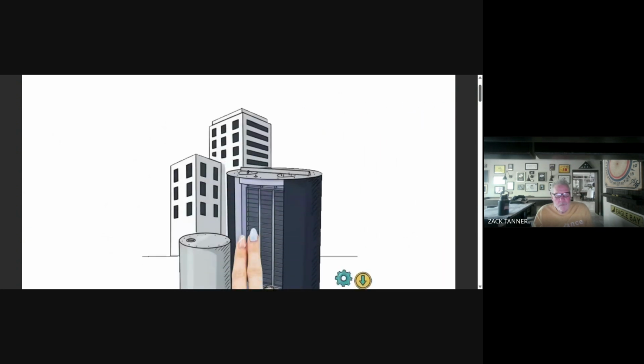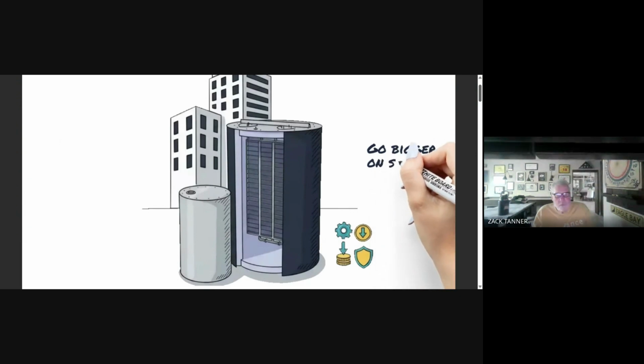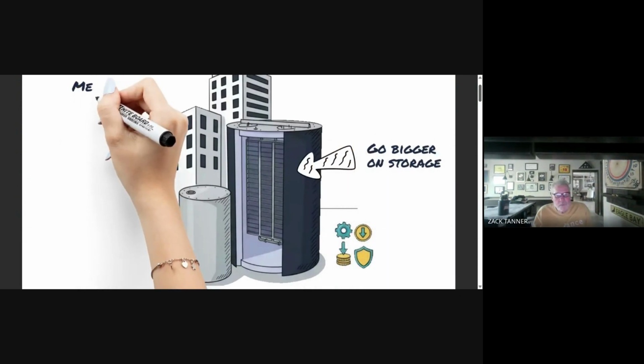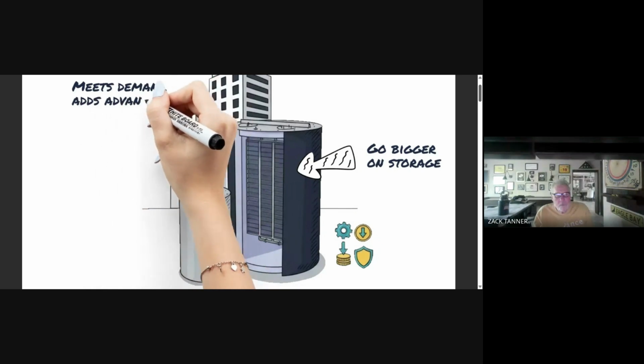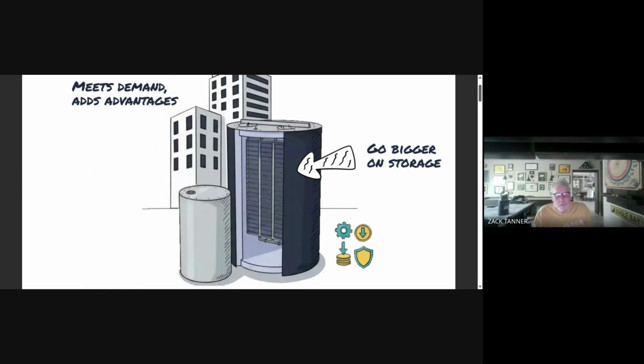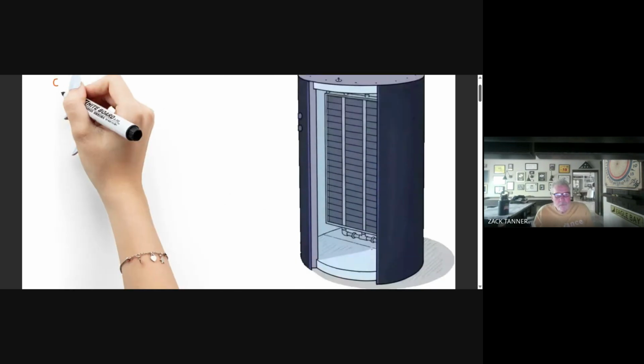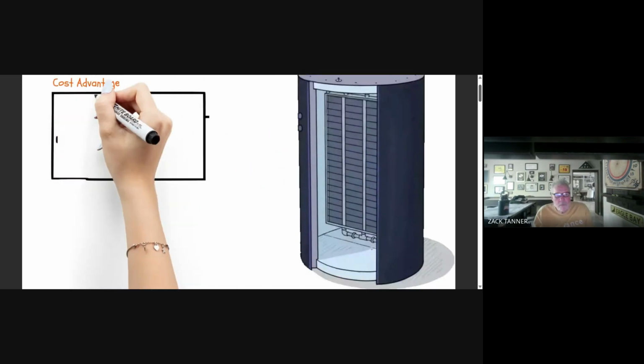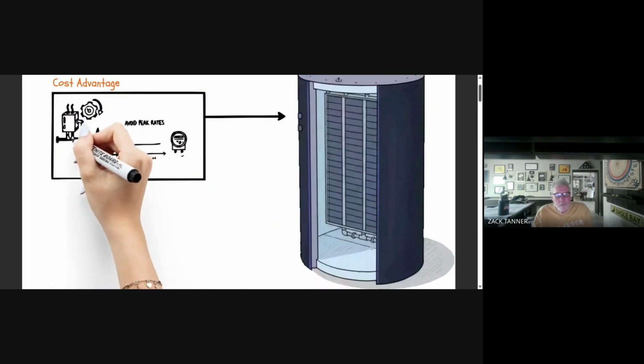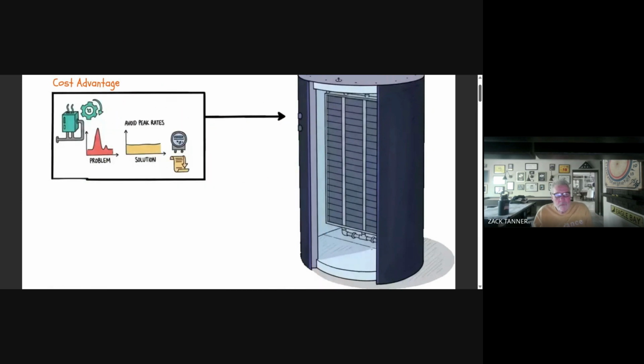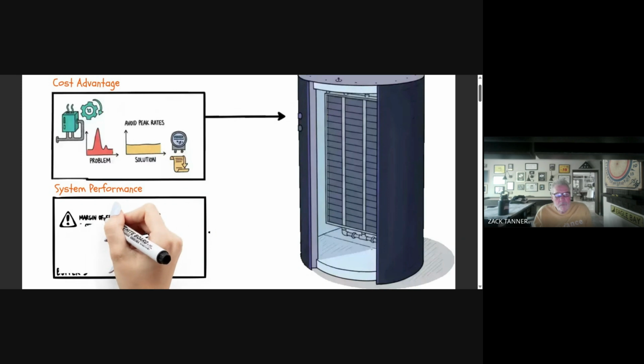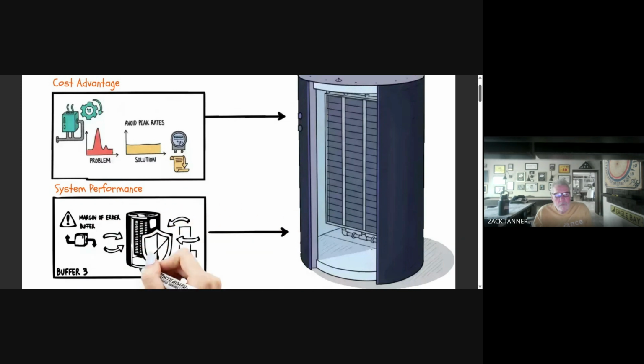You would love to use a larger thermal storage tank. Not only is it needed to meet the hot water demand of the building, but it also allows you to tap into several other advantages. It helps your existing energy source run more efficiently, saves money by avoiding peak rate cycles and lower demand charges for monthly maximum power usage, and increases the margin of error if the system isn't operating perfectly.